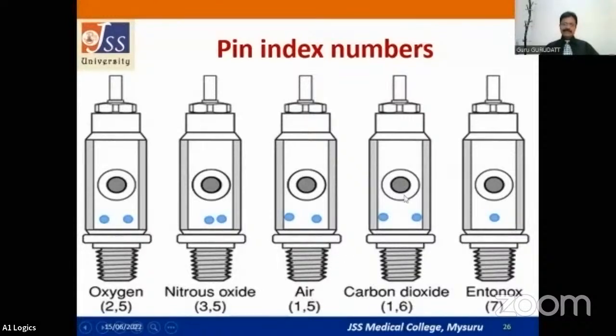And for carbon dioxide, the pin index number is 1.6. And for Entonox, I told you, it is a single hole. It is hole number 7, which overlaps hole number 3 and hole number 4.